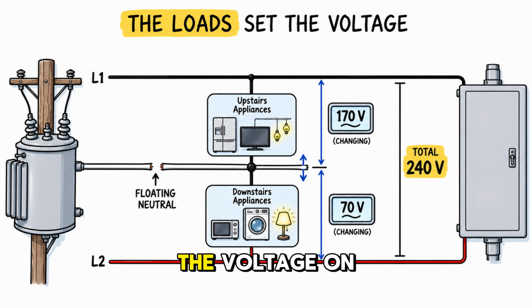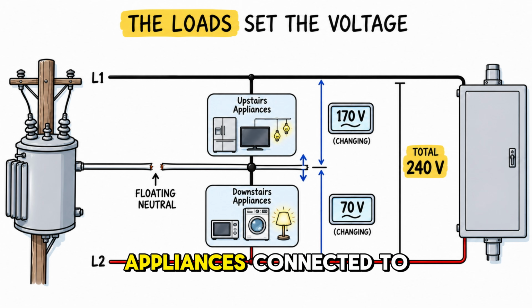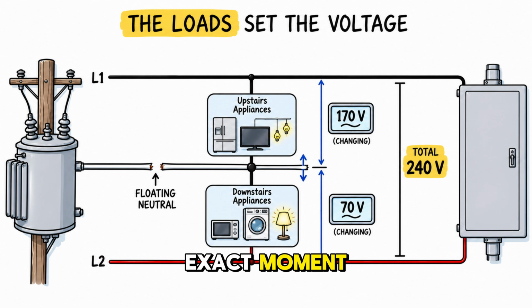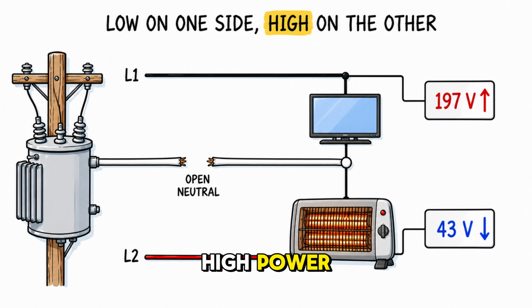In this situation, the voltage on each side is no longer controlled by the utility transformer. It is determined entirely by the mix of appliances connected to each side at that exact moment. Large appliances with high power demands cause the voltage on their side to drop, while small, delicate electronics cause the voltage on their side to skyrocket.